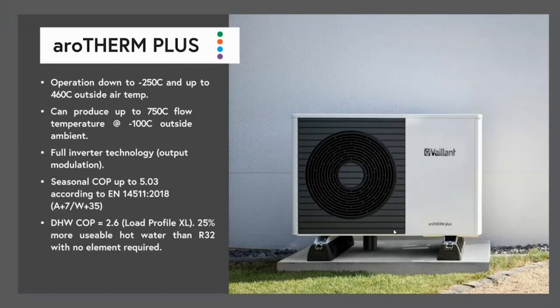And here is the, well, some of those numbers didn't come out very well, but we've already covered all this. So the unit operating down to -25 can produce a 75-degree flow temperature. Its seasonal efficiency to that standard is about 5.03, so very, very high efficiency is possible at 7 degrees air temperature and 35-degree water temperature. And it's got a COP on domestic hot water of 2.6. So these units can produce about 25% more usable hot water than an R32 unit, and they don't require any electrical element at all.